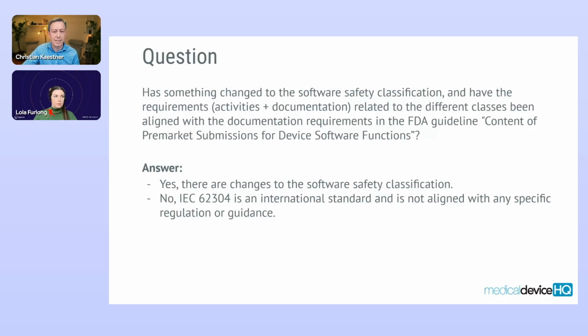You can say the FDA guidance identifies what documentation or information to provide in a submission, while 62304 is about the process you shall apply to your development work. So they serve two different purposes, and that's partly also why it's not possible really to seek perfect alignment. Hopefully, however, the process you apply following 62304 will result in the documentation required or expected by the FDA guidance.